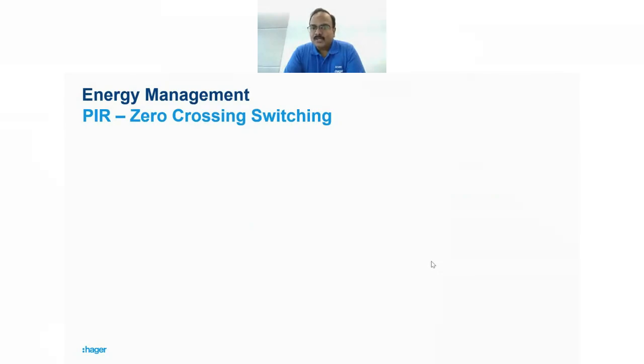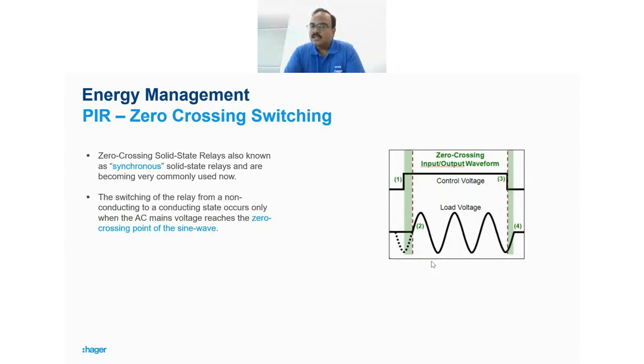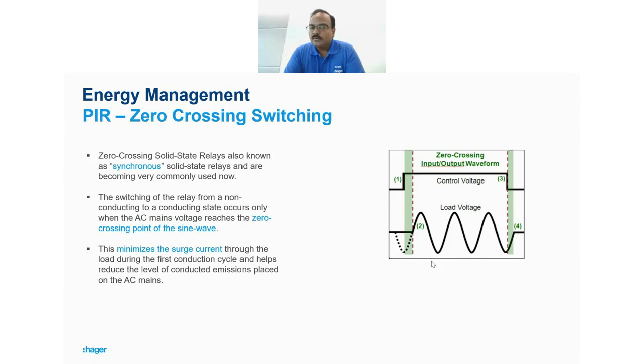In zero-crossing switching, when the control voltage detects movement and sends a signal to the relay, the relay waits — in microseconds or nanoseconds — until the AC curve reaches zero before switching on. This minimizes surge currents and is ideally suited for lamps with ballast for on/off function.